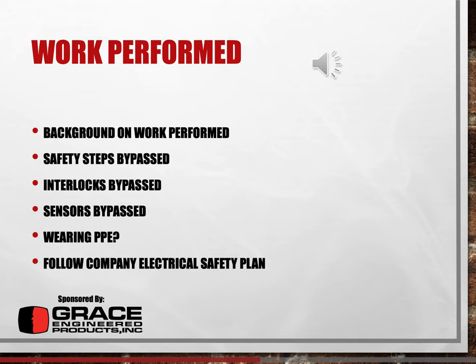Were the electrical safety program steps bypassed? Or did they fill out an electrical safety permit, or a work permit? Were the interlocks bypassed? Sometimes when doing testing, you have to bypass it to test the negative portion of the alarm, the alarm state. And did they forget to turn them back on or turn it back to normal?